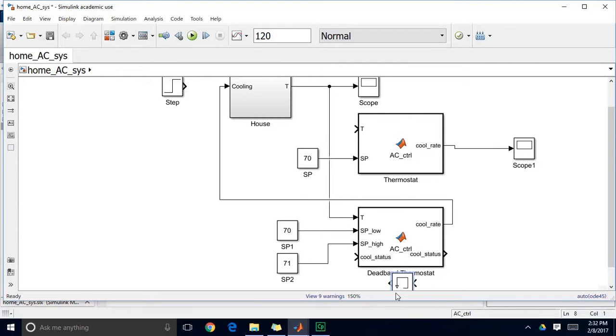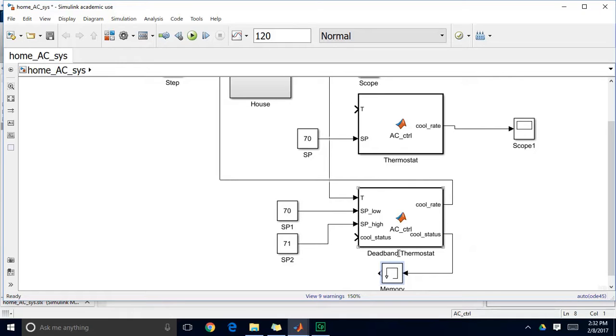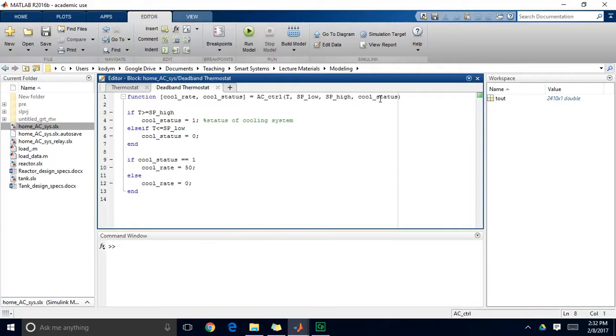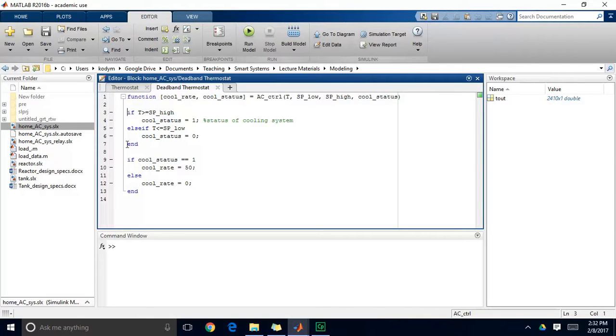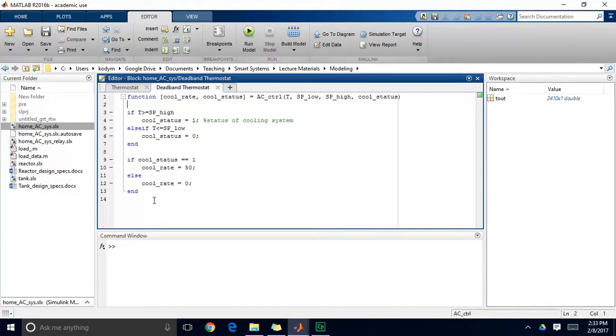And what I'm going to do now is I'm going to connect this cooling status to here. So this memory block, what it's going to do is it's going to take the cooling status of my air conditioning system. It will record that and it will store it. And then I can check the value of the previous cooling status in that same function. So I've done something a little bit funny here where this cooling status is both an input and an output to my function. And basically, the way that this will work is that if my temperature exceeds my high setpoint or it goes below my low setpoint, then in either of those events, I'll be changing the cooling status. But if neither of those things is true, if my temperature is between my low setpoint and my high setpoint, then I want to leave this cooling status alone. I don't want to change anything. So you can see there's no other line of code that sets the cooling status.